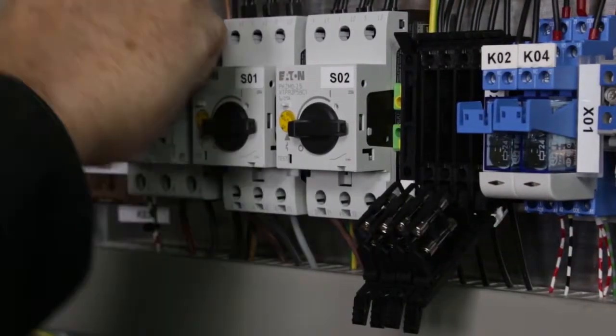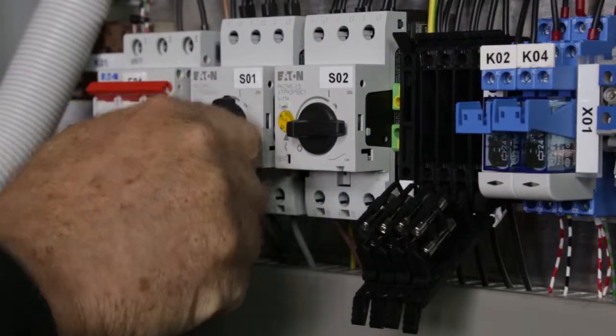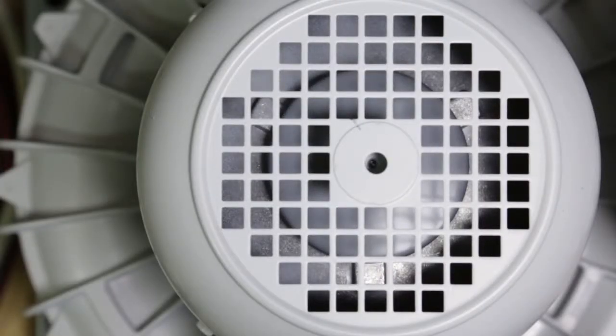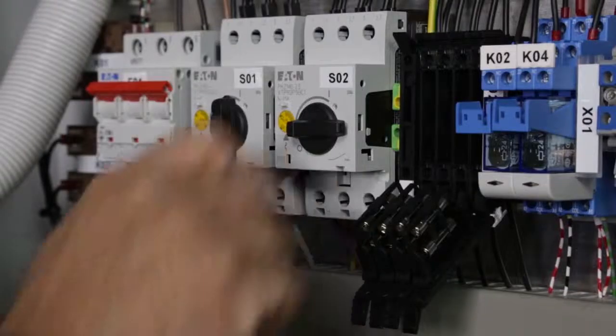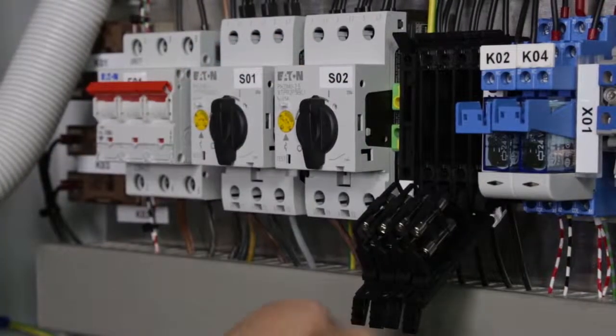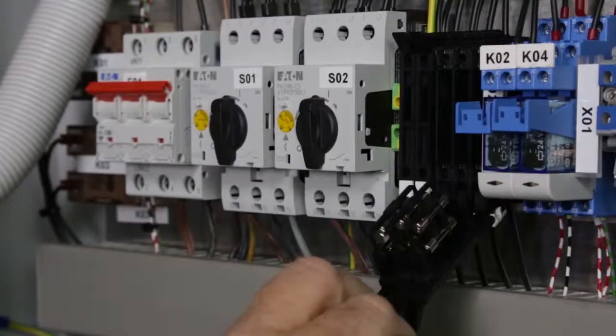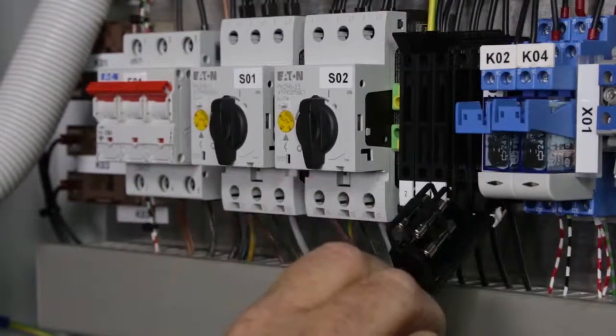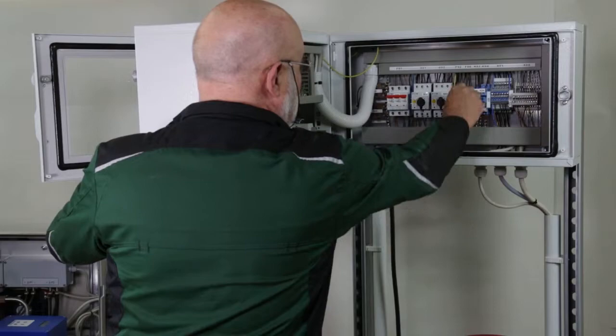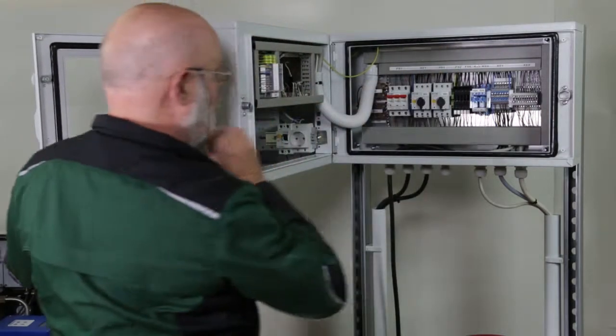Close the main fuse of the PFM 06ED. Close the motor protection switch of the injector. Check starting and rotating direction of the injector blower. Close the motor protection switch of the dilution air. Check the starting and rotating direction of the dilution air blower. Close all remaining fuses and the control unit.